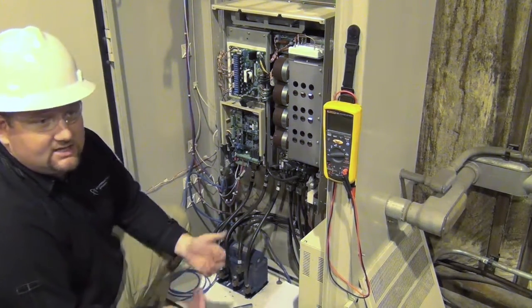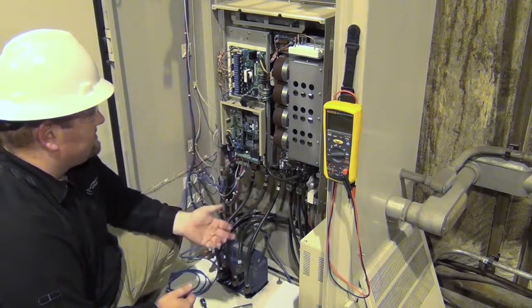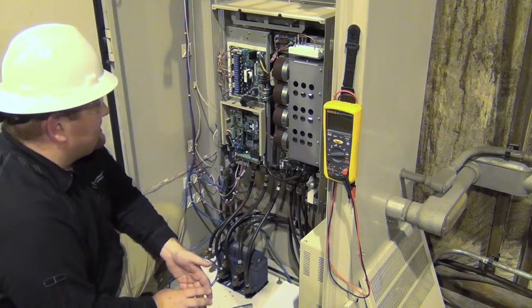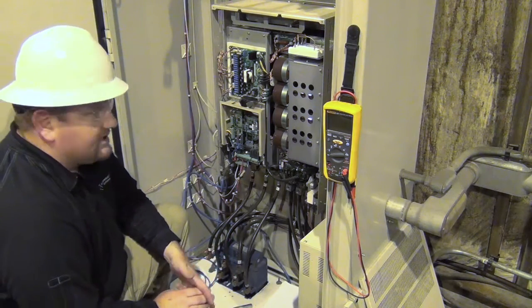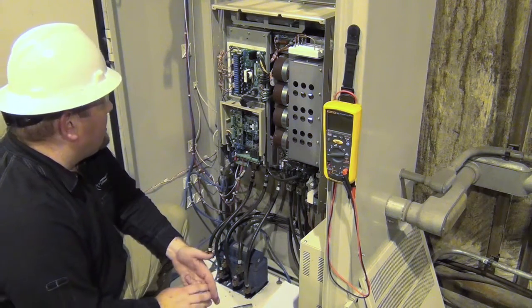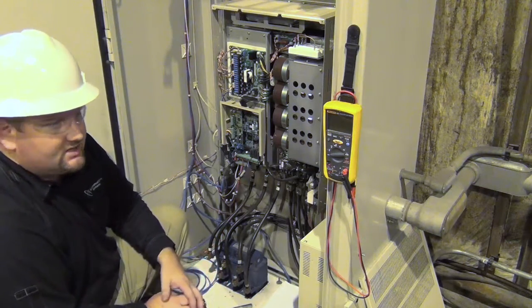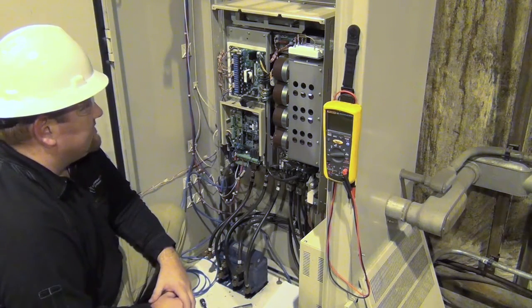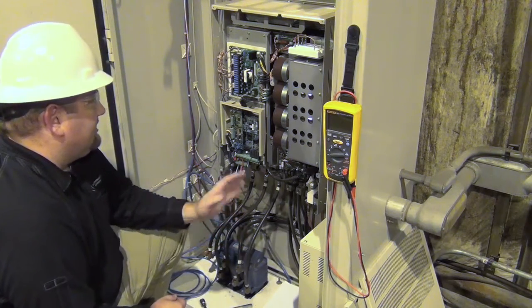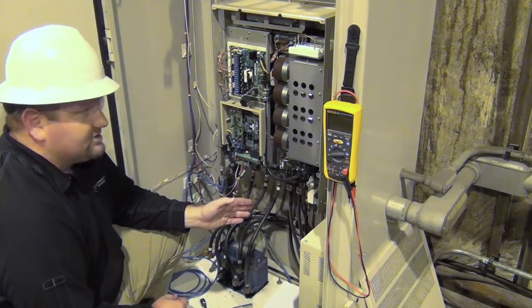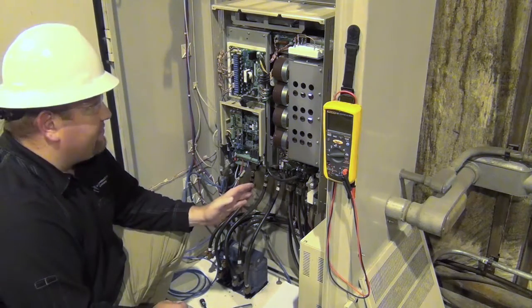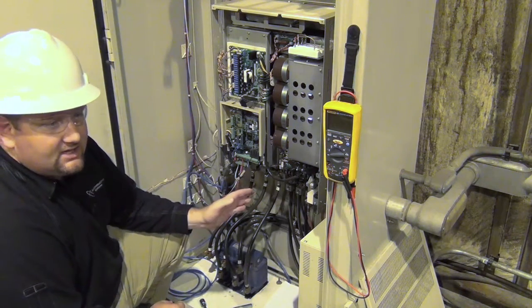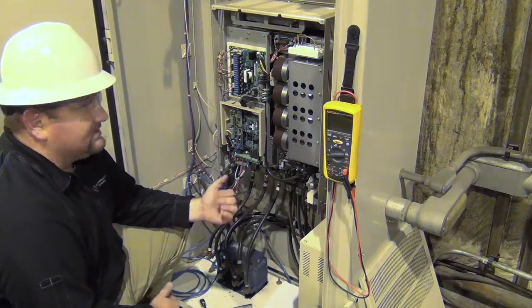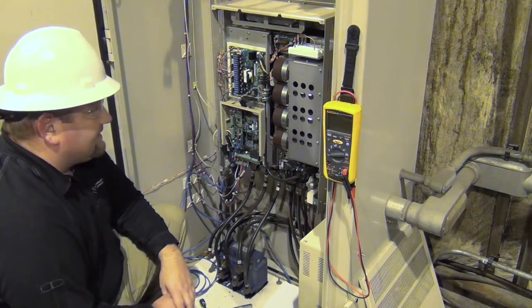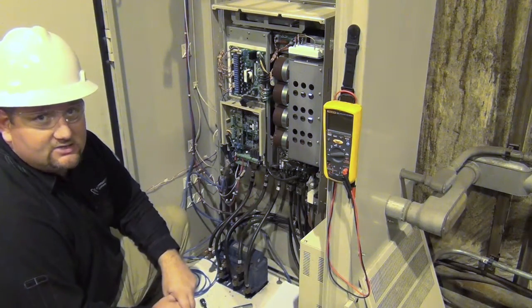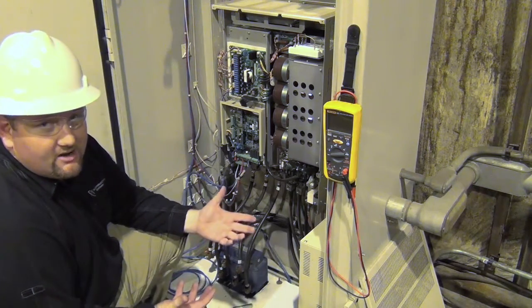We're also going to give a good visual inspection of all of the circuit boards. Again, looking for any signs of discoloration, especially on surface mount resistors or wire resistors, fuses that are on any of the boards. As far as the capacitors go, we're going to give them a good investigation, make sure that there's no signs of any fluid, that none of them have bulged or cracked, causing the electrolytic fluid that's inside the capacitor to leak out. If you find that, that would be a warrant for immediately taking the drive out of service and having it looked at or repaired.